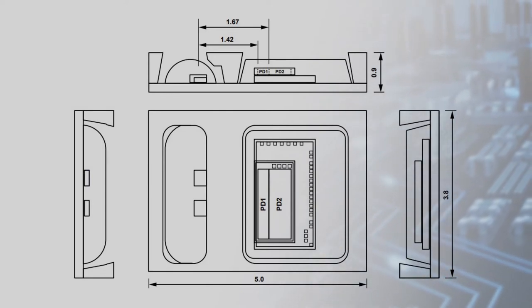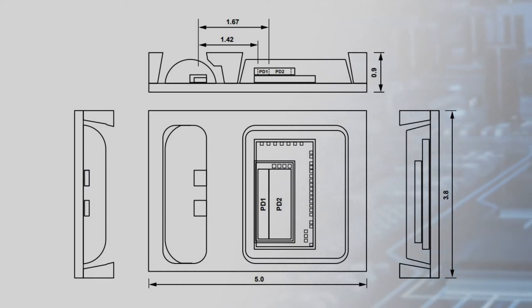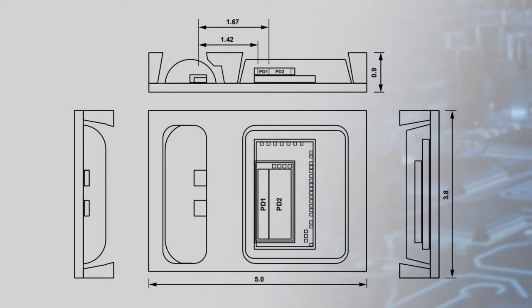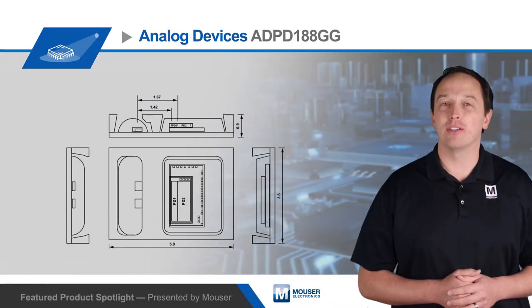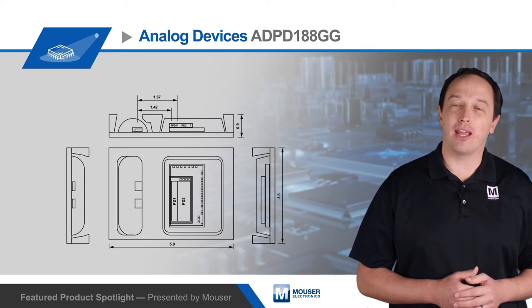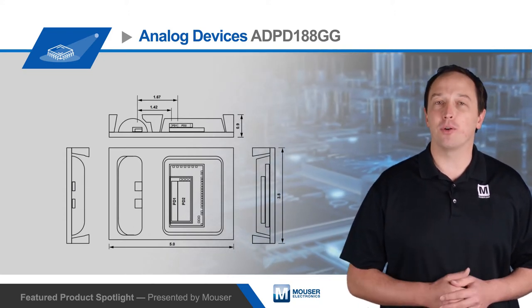It includes two 525 nanometer green LEDs and two IR photo detectors with IR cut filters. It uses synchronous measurements for best-in-class rejection of both AC and DC ambient light interference. The module is housed in a custom 24-terminal optical LGA package that ensures LED light pulses pass through the subject before entering the photodiodes.